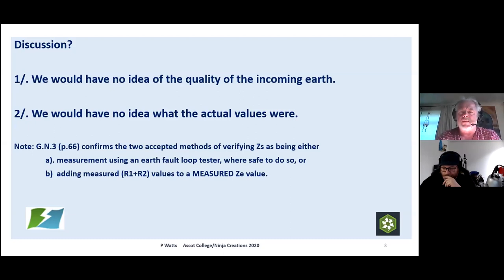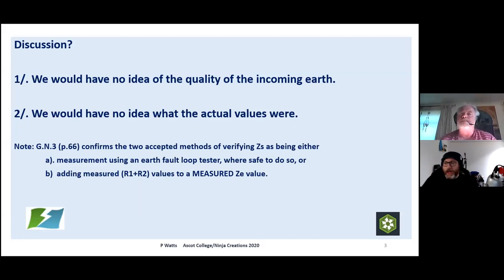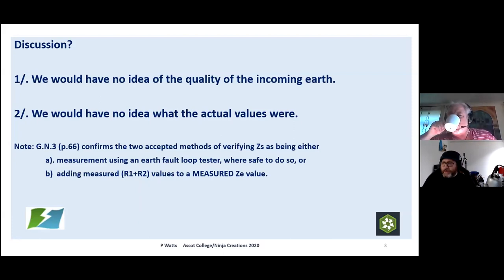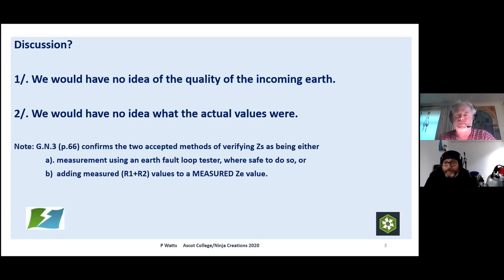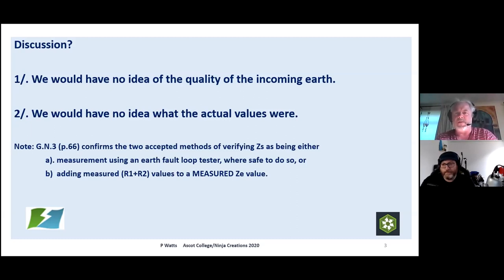So we cannot just take an inquired value and add on a calculated value. It's got to be that at least one part — the incoming Ze from your distributor — has to be a properly measured value. Because if we go by inquiry and then add on calculated values without actually testing, we've had discussions where guys have gone to an installation that had no earth at all — a couple of people said 'yeah, I've come across that.' If we don't actually test, that's the sort of thing that's going to happen.